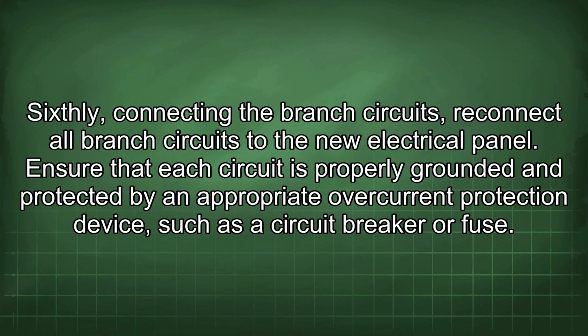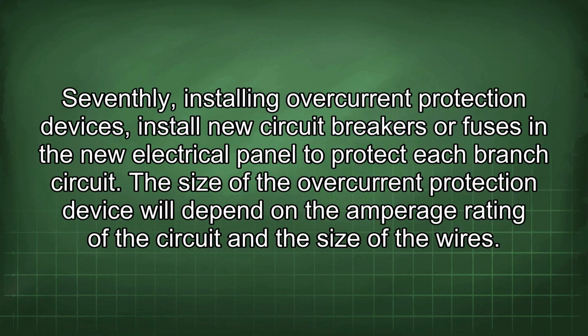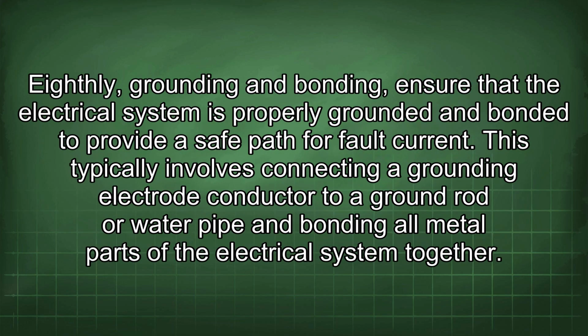Sixthly, connecting the branch circuits. Reconnect all branch circuits to the new electrical panel. Ensure that each circuit is properly grounded and protected by an appropriate overcurrent protection device, such as a circuit breaker or fuse. Seventhly, installing overcurrent protection devices. Install new circuit breakers or fuses in the new electrical panel to protect each branch circuit. The size of the overcurrent protection device will depend on the amperage rating of the circuit and the size of the wires.